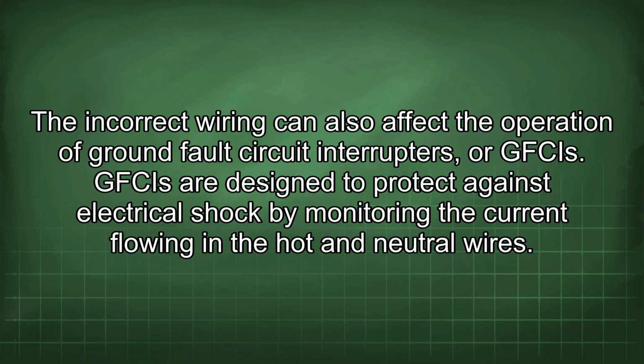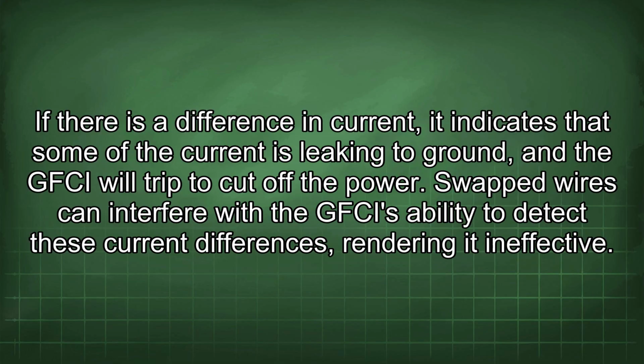The incorrect wiring can also affect the operation of ground fault circuit interrupters, or GFCIs. GFCIs are designed to protect against electrical shock by monitoring the current flowing in the hot and neutral wires. If there is a difference in current, it indicates that some of the current is leaking to ground, and the GFCI will trip to cut off the power. Swapped wires can interfere with the GFCI's ability to detect these current differences, rendering it ineffective.